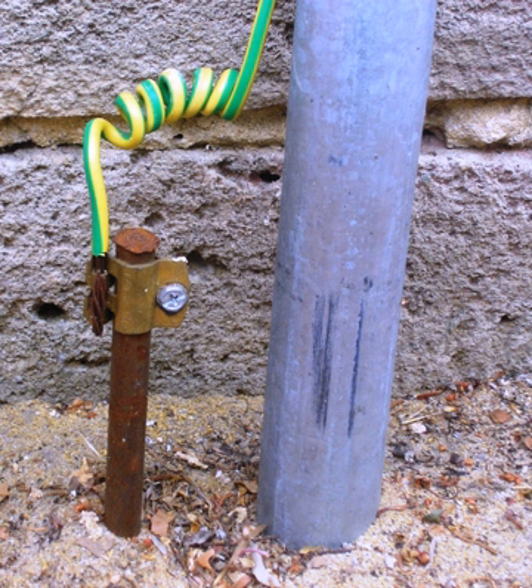Permanently installed electrical equipment, unless not required to, has permanently connected grounding conductors. Portable electrical devices with metal cases may have them connected to earth ground by a pin on the attachment plug, see domestic AC power plugs and sockets. The size of power grounding conductors is usually regulated by local or national wiring regulations.